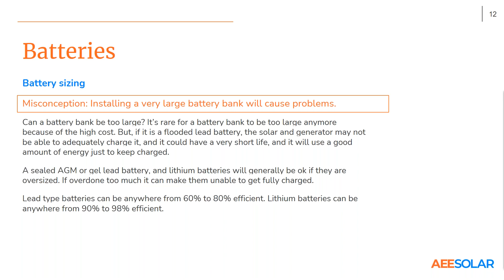Sealed AGM gel lead batteries have a different construction, different alloy material in their plates, and tend to be much less of an issue with that. They're much more efficient, and you can recharge them with a small current and get them up to a full state of charge. Lithium batteries, same way. They're quite efficient, so you can get them up to a full state of charge with a smaller system. So oversizing those is generally not as much of an issue unless you really overdo it.